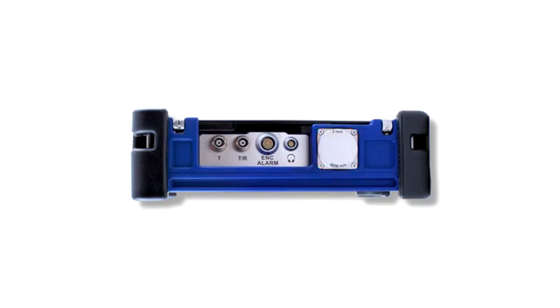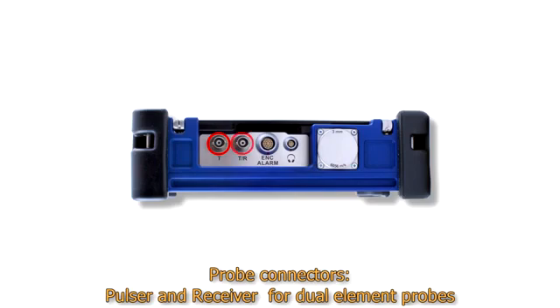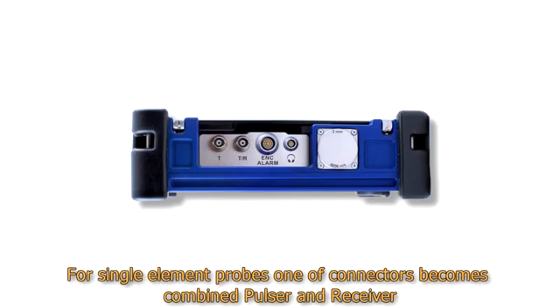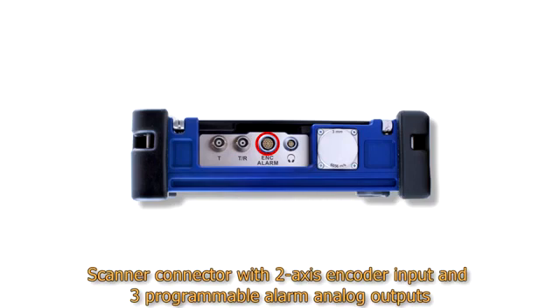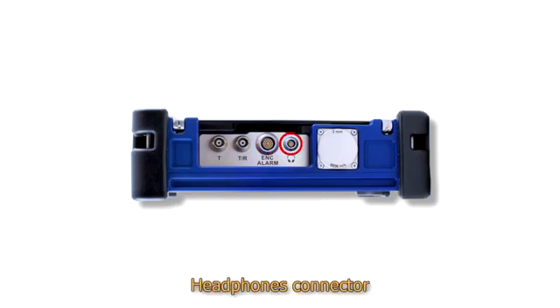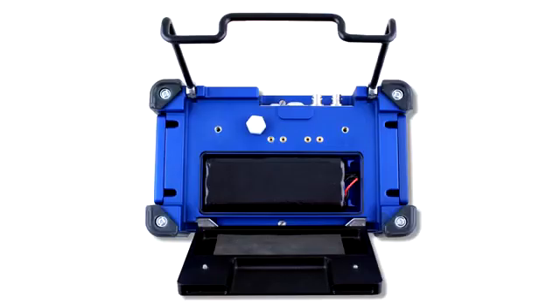Also, in the special recess, the most frequently used connectors are situated: probe connectors, pulser and receiver for dual element probes. For single element probes, one of the connectors becomes combined pulser and receiver. There's also the scanner connector with 2-axis encoder input and 3 programmable alarm analog outputs, and a headphones connector. On the rear panel, the removable battery compartment cover with an 8 hours rechargeable battery under it is placed.